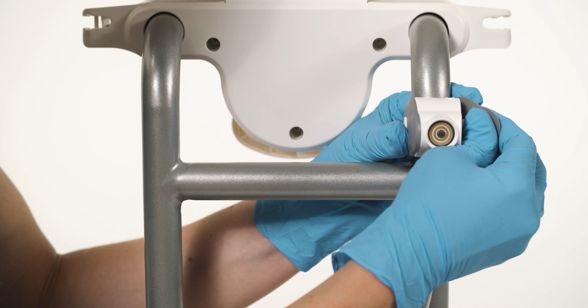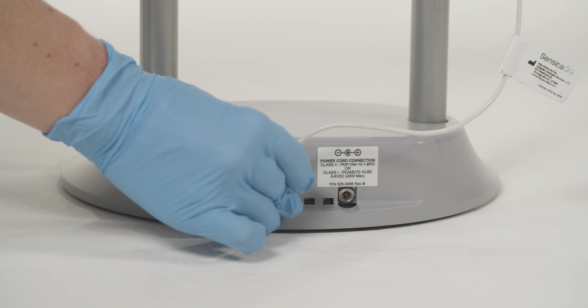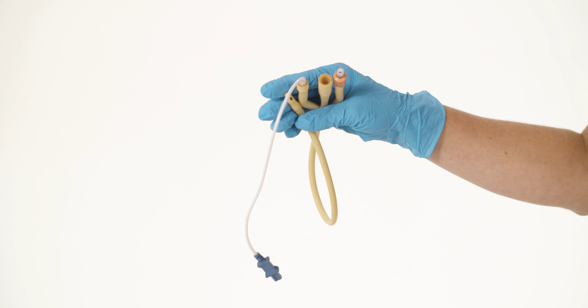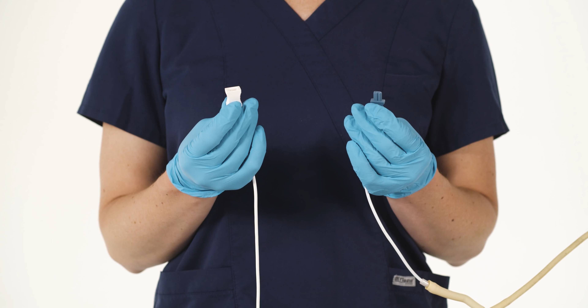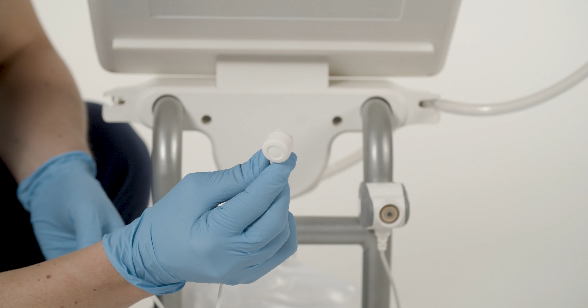The Sensica urine output system can display a continuous measure of core bladder temperature if the patient has a temperature-sensing Foley catheter. The temperature monitor module is attached above the crossbar and plugged into the USB port on the base. To use the monitor, simply connect the temperature-sensing Foley catheter cable to the Sensica temperature sensor cable. Then attach the magnetic connector to the temperature monitor module.